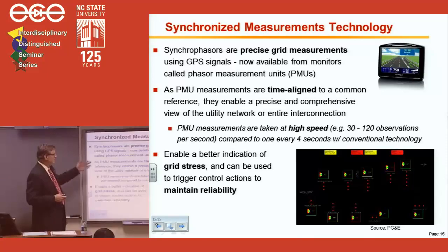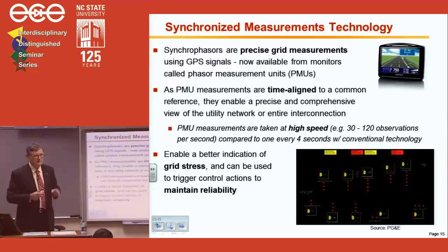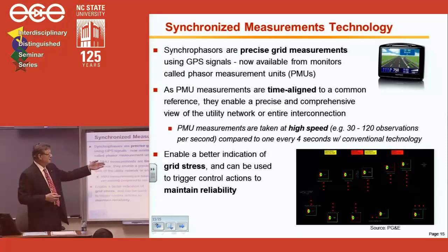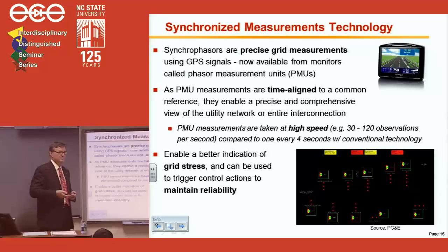The bottom line is I always say this is not rocket science, it's actually a relatively simple technology. What you do is get your GPS signal and synchronize the measurements across the grid. Synchronization is done in a matter of microseconds, that's actually the standard, 1 microsecond. And you have the ability to monitor 30 to 120 observations per second. Think about EMS SCADA systems that sometimes refresh every minute or every two. You now suddenly have a system that can do a lot more.